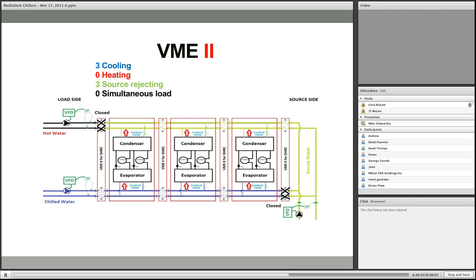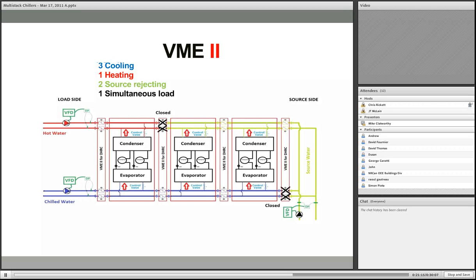So here we've got 3 in cooling. So on this end, that's my common source sink. On this end, my chilled water, and up here, my hot water. And in this scenario, I need 3 modules in cooling and none in heating. So I can close this set of valves and put all 3 modules to the cooling load. I can close this valve, and rather than rejecting my heat to the heating load, I reject it to the source sink.